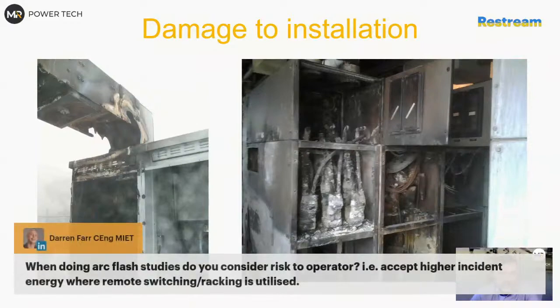Well, this is a good question from Darren. When doing arc flash studies, do you consider risk to the operator and accept higher incident energy where remote switching or racking is utilized? I would say this is still a risk. This is called an arc flash risk assessment. Yes, there is a risk assessment behind this. For me, risk assessment is a very gray area topic because, as far as I know, risk assessment is where you calculate the probability of things happening. You know the hazard from calculation, and overall risk or severity, however you call it, and you have overall risk results.